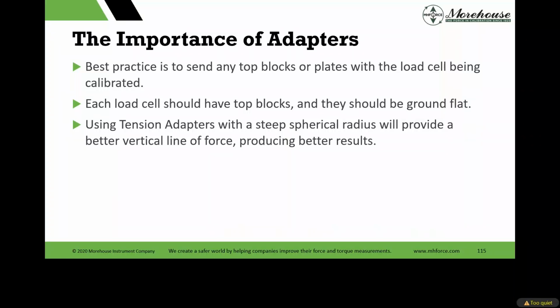As a best practice for other adapters, wrapping this section up on the adapters, send top blocks or plates with the load cell being calibrated. Each load cell should have top blocks and they should be ground flat. Using tension adapters with a steep spherical radius will provide a better vertical line of force, producing better results.